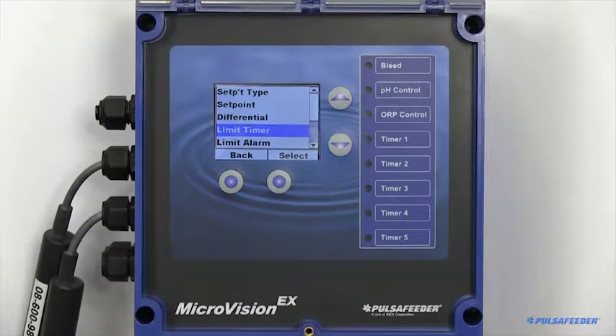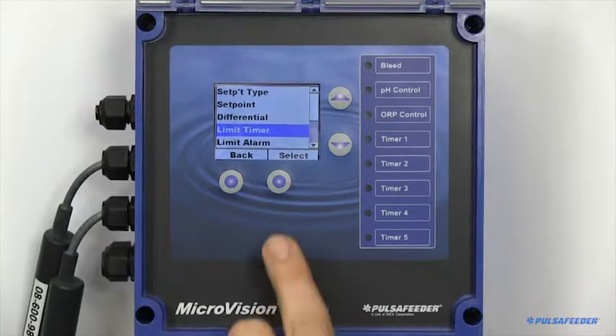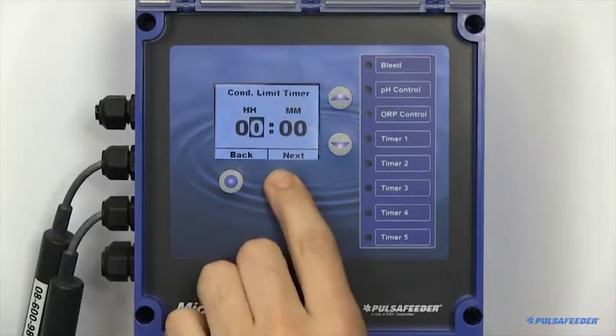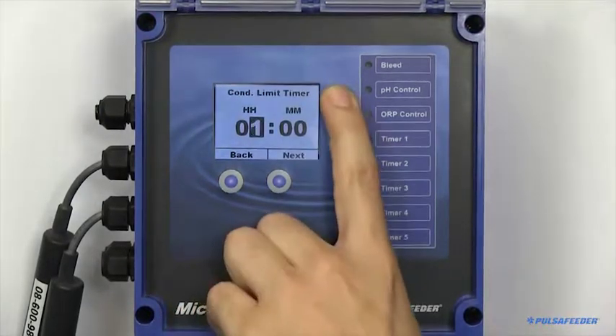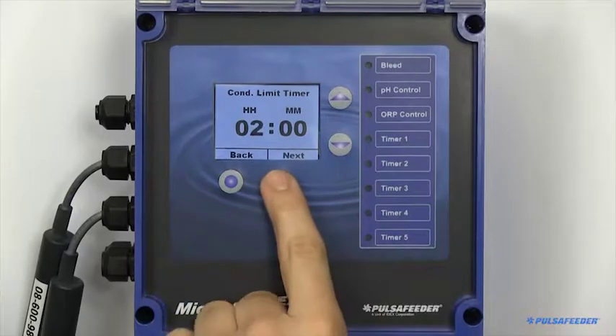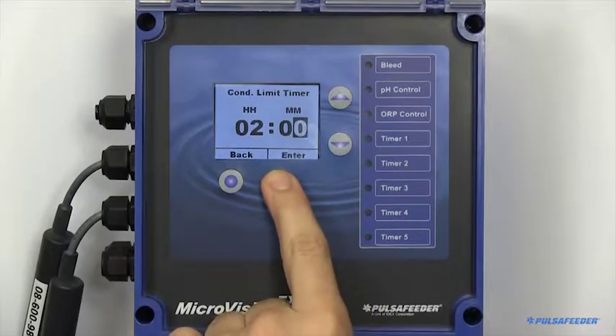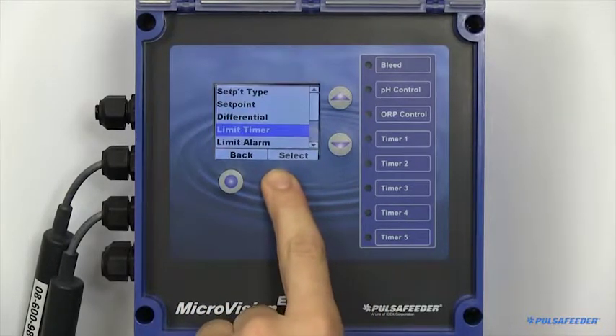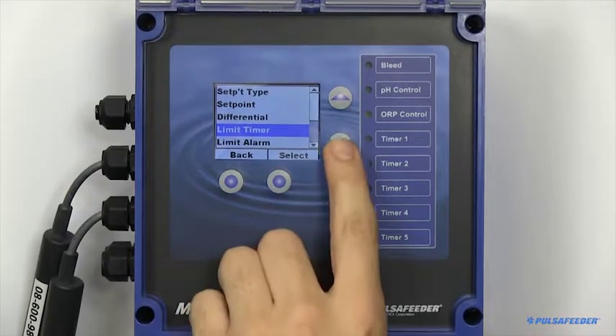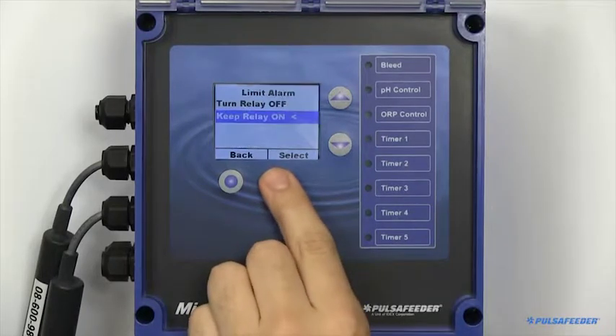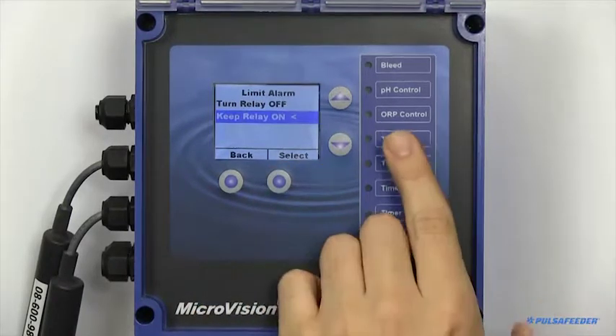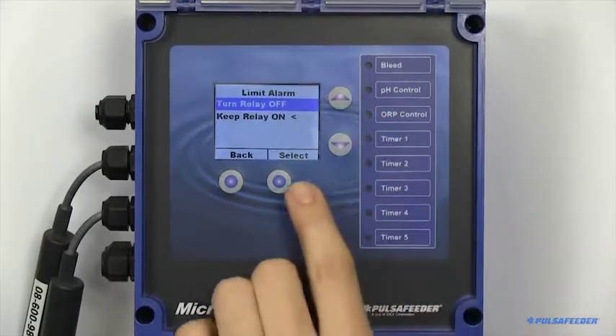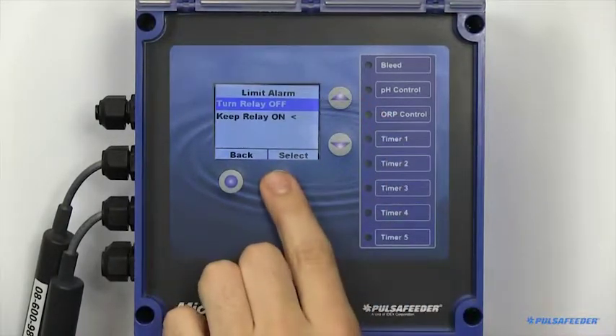Limit timers can also be enabled. The limit timer is the maximum amount of time you would like the relay to remain on until an alarm is triggered. You can set whether you would like the relay to remain on or turn off upon an alarm state triggering here.